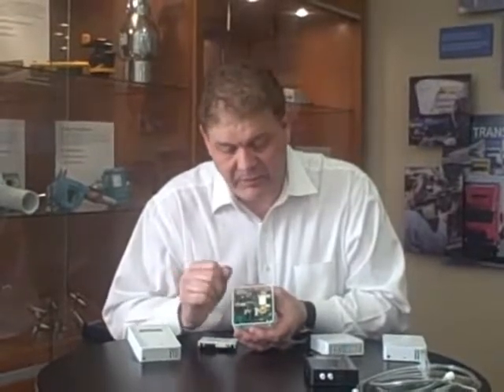Let's have a closer look inside. The PCB is identical in both units. Here's our CO2 sensor — this is our 6613, which is a single-channel self-calibrating sensor, and we warranty the calibration on CO2 for life. It also has the passive thermistor, just like the non-display version.